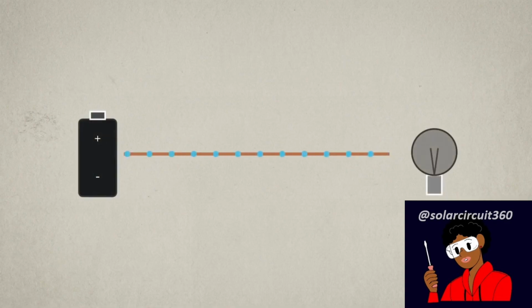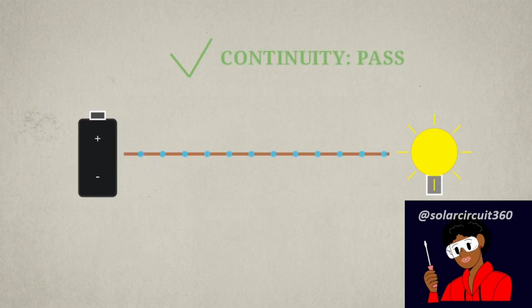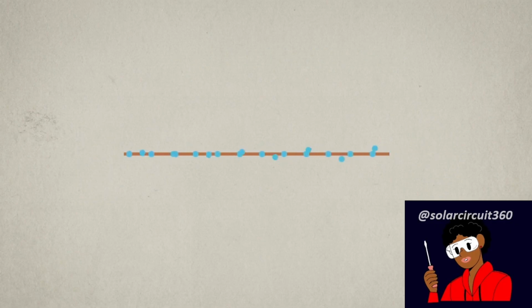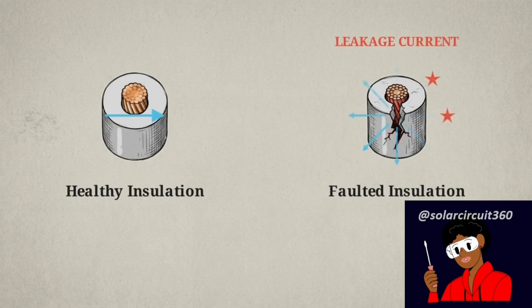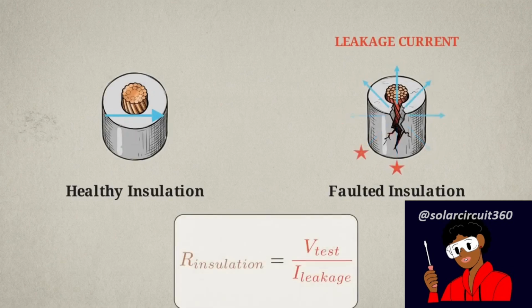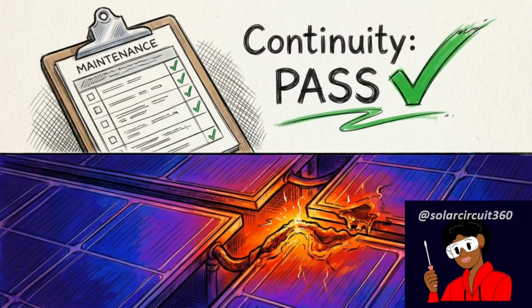A continuity test verifies the mechanical integrity of the circuit, confirming that current has a path to flow from one end of the copper conductor to the other. An insulation test, however, measures the ability of the surrounding material to contain that current and prevent it from escaping into the environment. A cable can show perfect continuity while insulation fails. In high-voltage DC systems, a simple continuity pass provides zero data on the safety jacket's health. The Megger tester calculates the specific microscopic current that successfully breaches that outer jacket. Relying on continuity checks alone for solar array maintenance creates a false confidence in wiring that may already be electrically compromised.